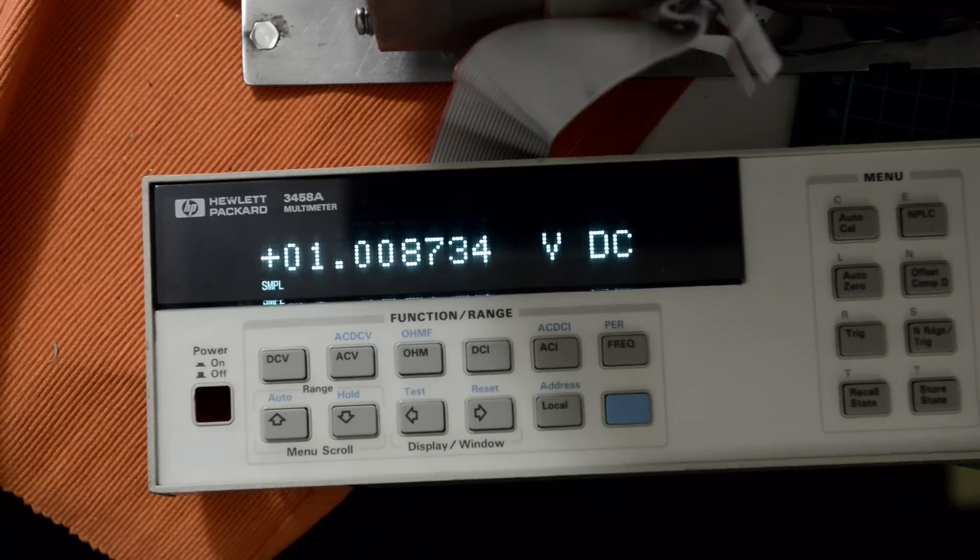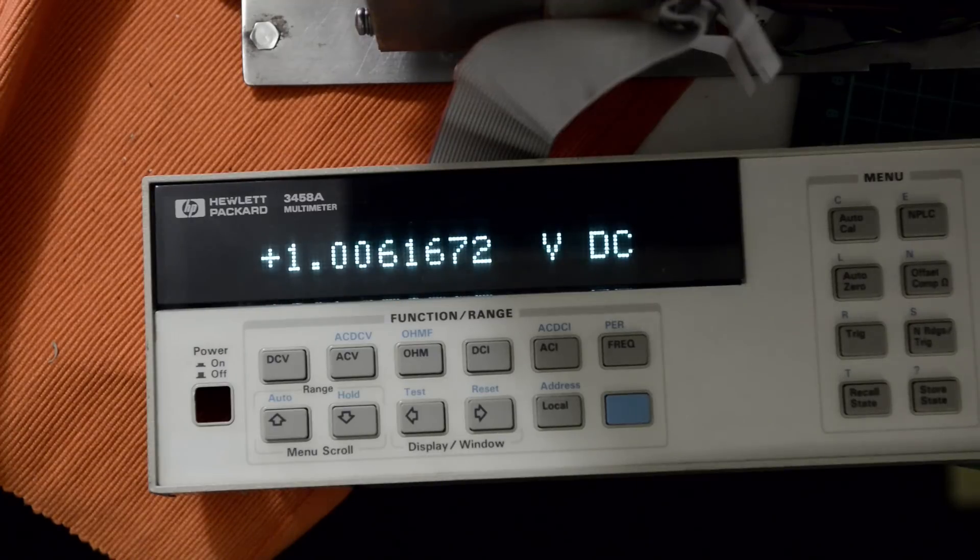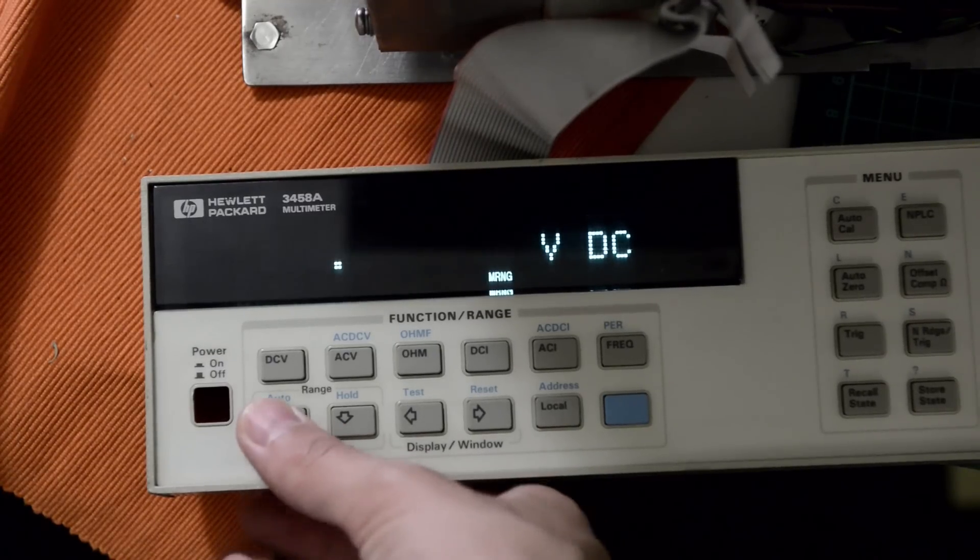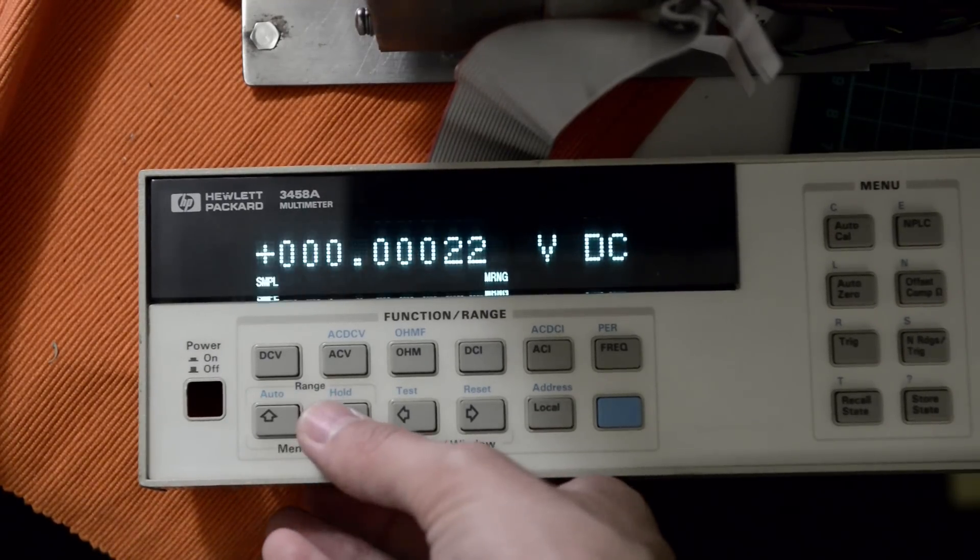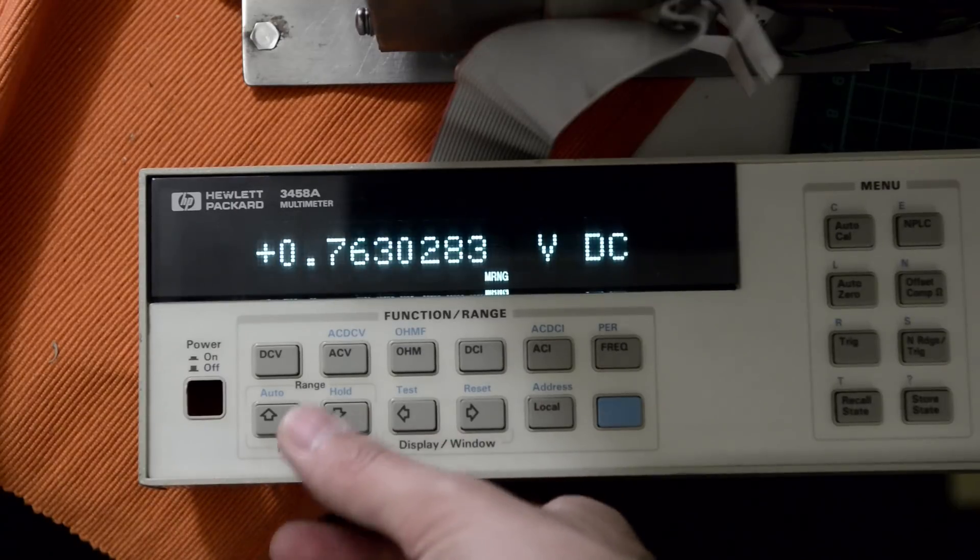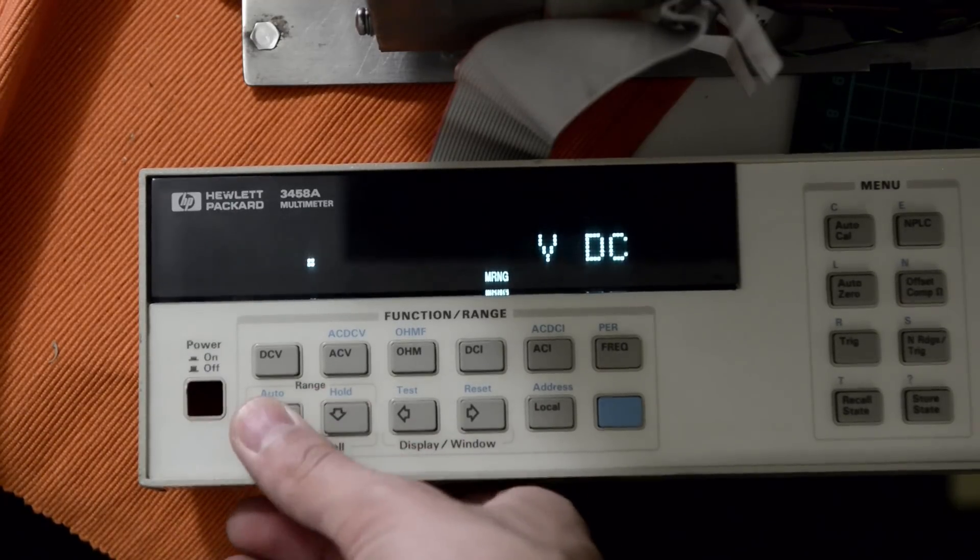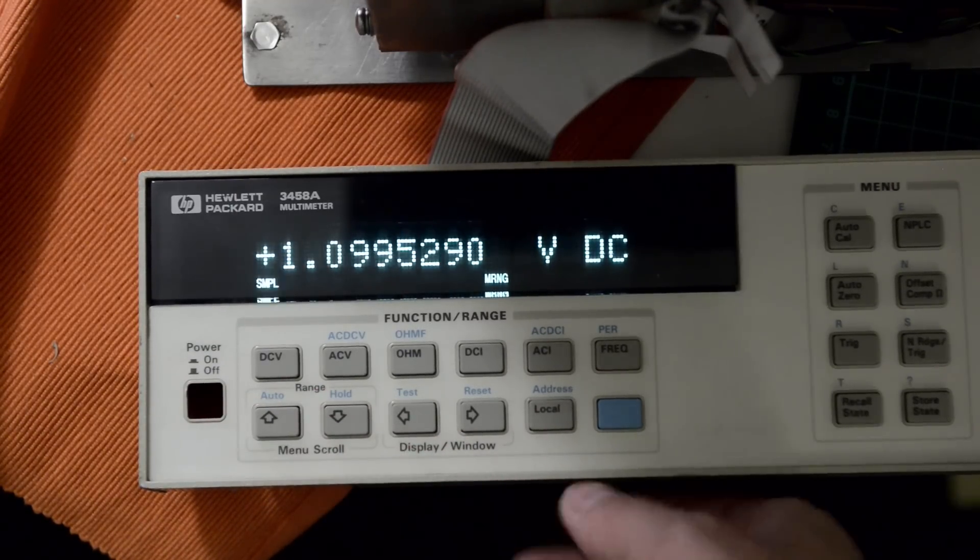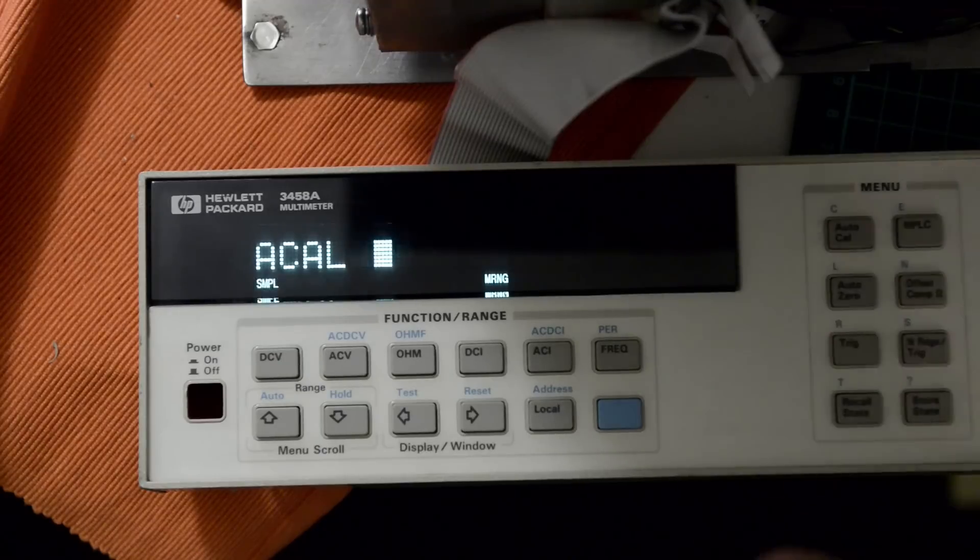Now disconnect the probe. So now it's in high impedance mode, reading some charge, just as I expected. And AutoCal voltage, enter.